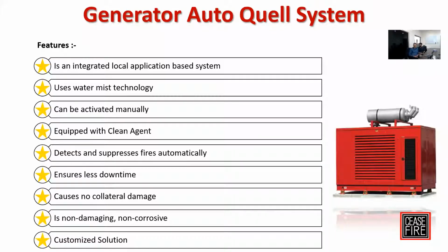That's the generator auto Quell system. The salient features or the USP of the system is an integrated local application based system. So you are really not dependent on any pump or any third party supply of water. It is a self-sufficient, self-contained system, and it will work automatically. It uses water mist technology. It can be actuated manually. It is equipped with the clean agent. We call water a clean agent because water does not create any problem inside the generator area since we are using water mist.